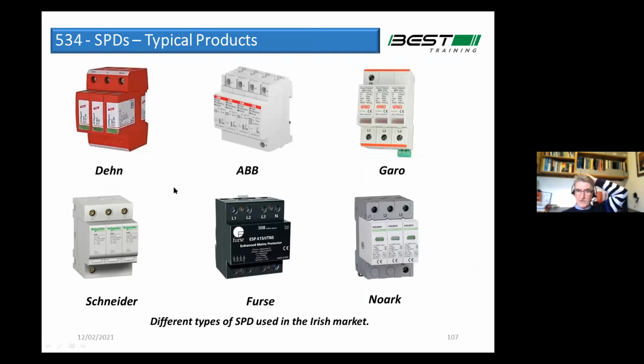And then the next area, of course, we mentioned that there's a huge growth in the volume of... Part 44 talks about transient overvoltage protection, and basically how we protect against transient overvoltage. We use surge protection devices. They've been around a long time. In the past, we specified these as part of the lightning protection system, but they're now clearly embedded in the wiring rules, telling us in Chapter 44 that we should be assessing the risk of transient overvoltage and putting these in. In fact, they're mandatory in most locations.